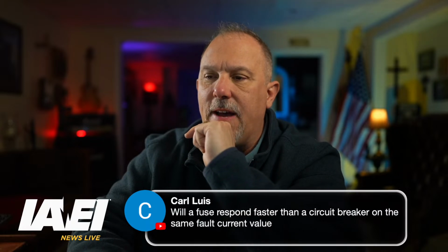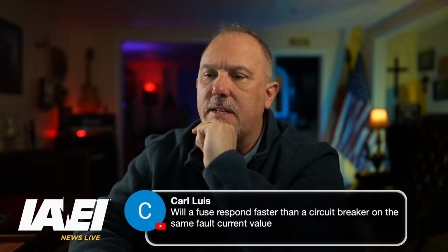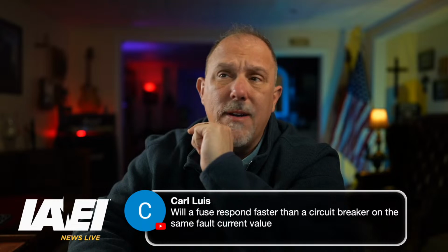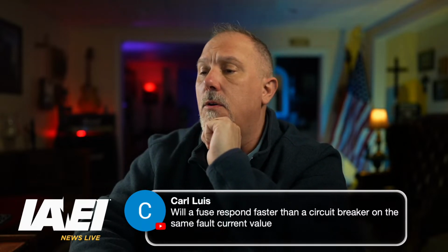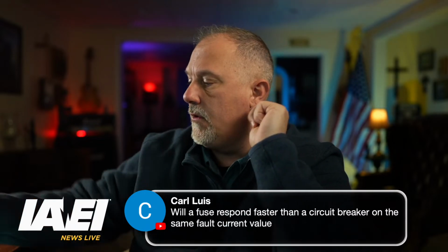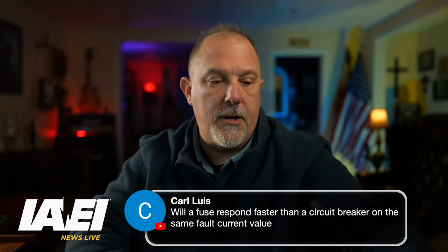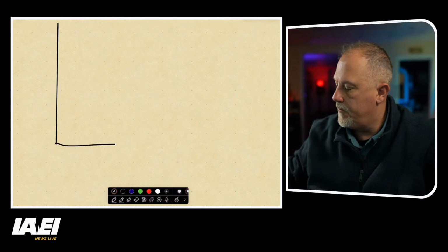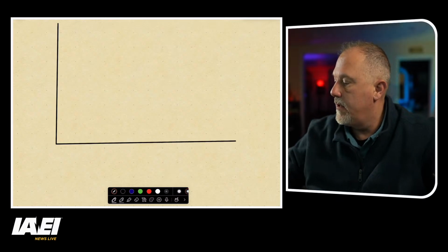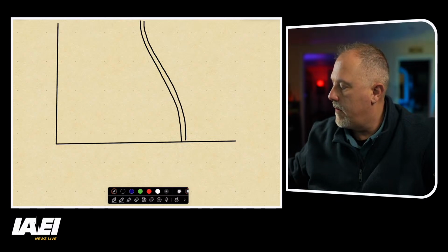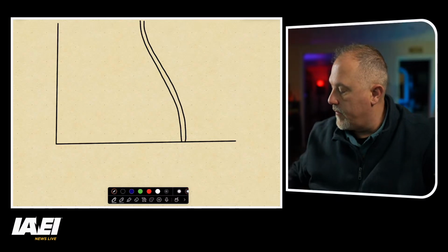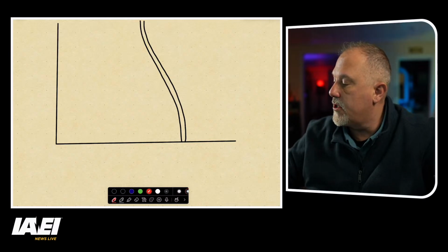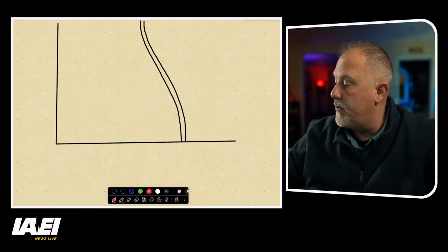Will a fuse respond faster than a circuit breaker on the same fault current value? Carl, it depends. If you think about a fuse and a circuit breaker, if I drew two curves, let's draw a fuse curve. And let's draw a circuit breaker curve. Ooh, I'm going to use red. And I have the circuit breaker and fuse at the same limit.